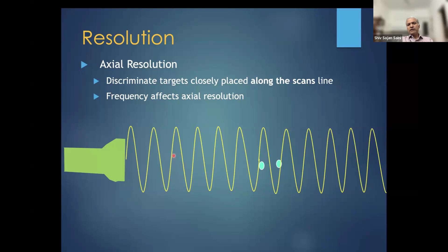Now look at this. We have taken a high frequency probe, where there is a shorter wavelength, and now these two structures are falling in two different wavelengths. This structure is hit by, say, the sixth or seventh wave, and this structure is hit by the next wave. So now the machine is able to differentiate these two structures as two different objects. So what do we learn? That our axial resolution depends upon the frequency of the probe, and the higher the frequency, the higher the axial resolution.